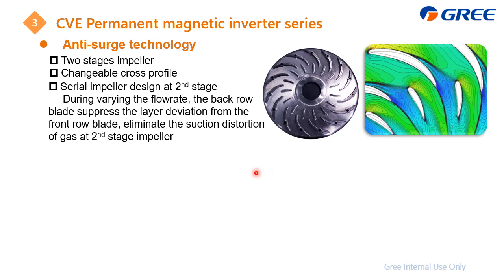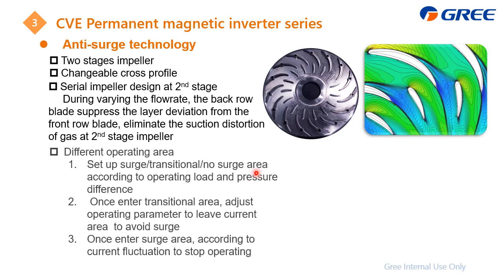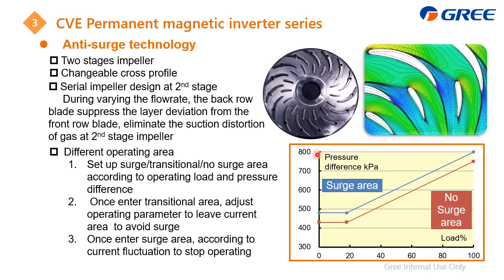Besides, on the system control, just like this graph, you can see that according to different load and different pressure difference between the suction side and the discharge side, we create the no surge area and the surge area, and also there is a transitional area.